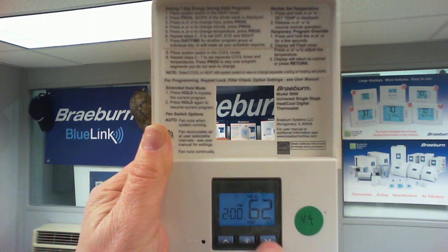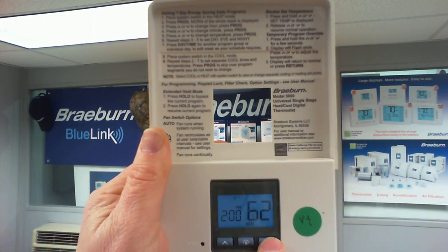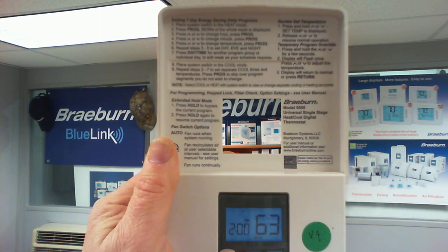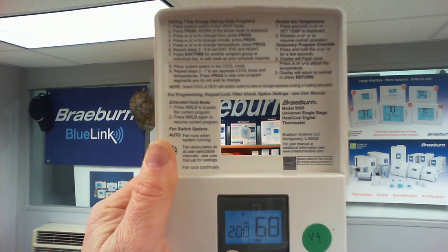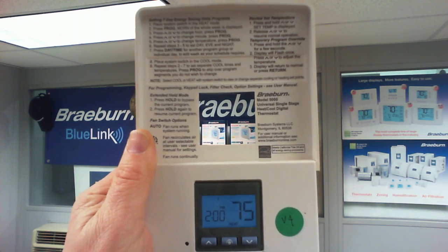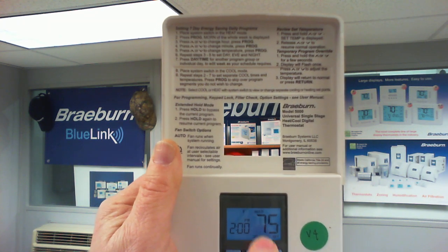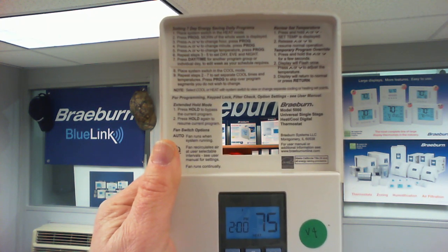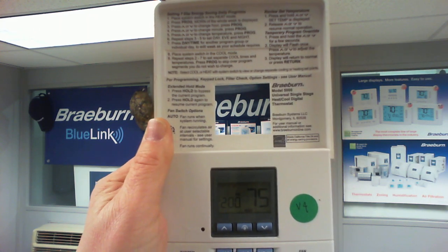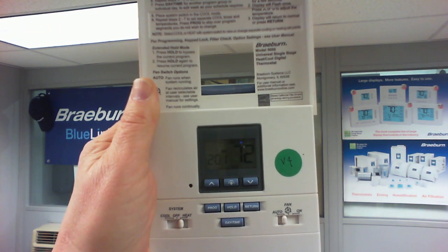If you hold it long enough, it will start blinking, and then it will allow you to change that set temperature. So you can raise it up or down to the number that you want. We're going to set this up to 75. After you've set it to the number you want, you'll see the hold and the set are flashing. Then just let it alone. After about 10 seconds or so, that number will be saved and the display will go back to showing you the current room temperature. It is now going to hold at 75.